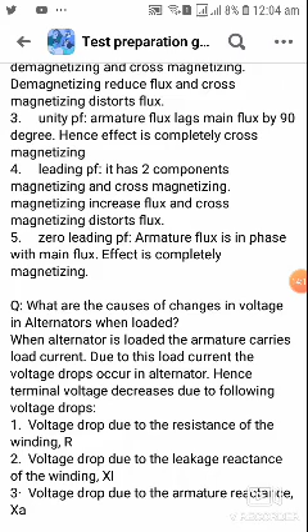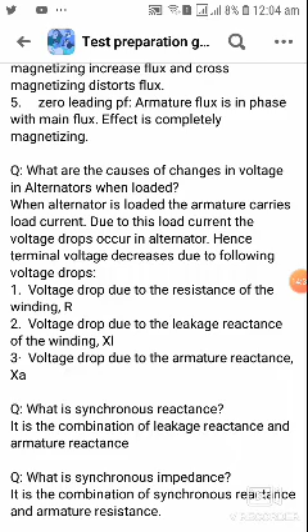Number 4. Leading power factor. It has two components, magnetizing and cross magnetizing. Magnetizing increases flux and cross magnetizing distorts flux. Number 5. Zero leading power factor. Armature flux is in phase with main flux. The effect is completely magnetizing. Question number 28. What are the causes of changes in voltage in alternators when loaded?